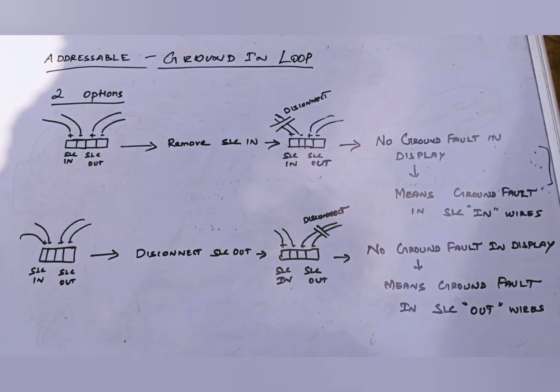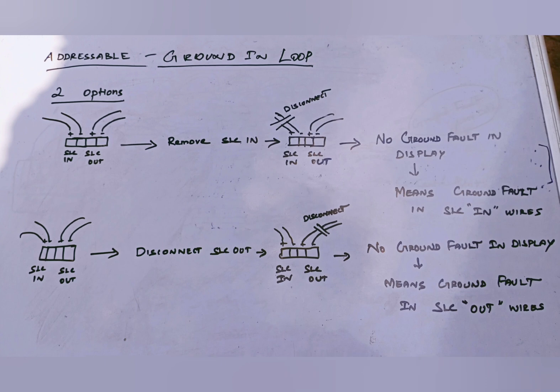First one, when you will disconnect SLC in pair of wire. If FACP will not show the ground fault exists, which means SLC in has the ground fault. When you will disconnect SLC out pair wire. If FACP will not show the ground fault exists, which means SLC out has the ground fault. Vice versa.